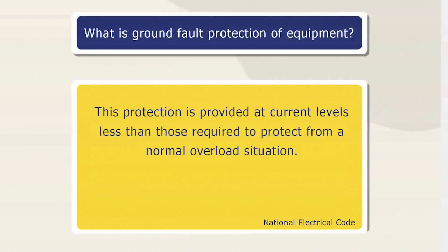This protection is provided at current levels less than those required to protect from a normal overload situation. So you're going to clear a fault quickly when it goes to ground, and when you have an overload, it's going to take a little bit longer and you're going to get more heating. So we want to see that ground fault, we want to protect it right away.